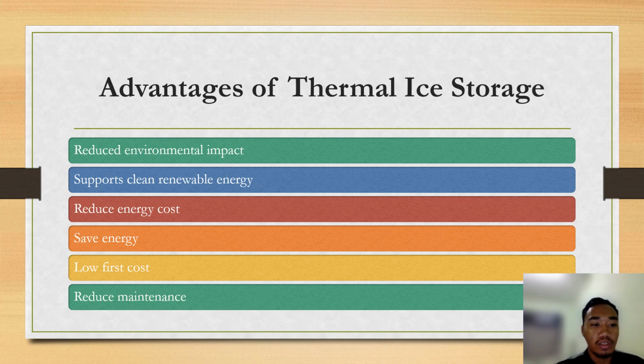The fourth advantage of thermal ice storage is it can save energy. When the system is designed to take advantage of the low supply water temperature from an ice storage system, energy use is significantly reduced. Low temperature chilled water utilizes low horsepower pumps but still can provide low temperature air with lower horsepower fans. The efficiency of the chiller can be increased due to lower condenser temperature at night.